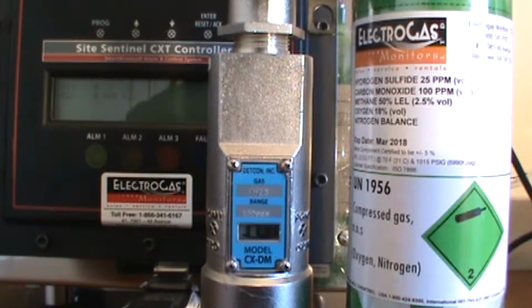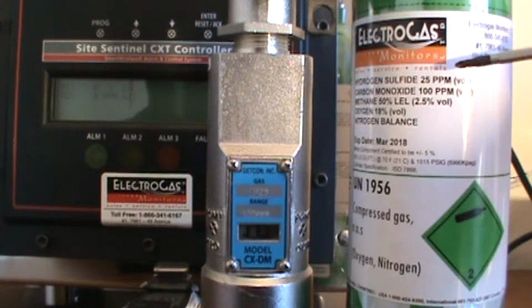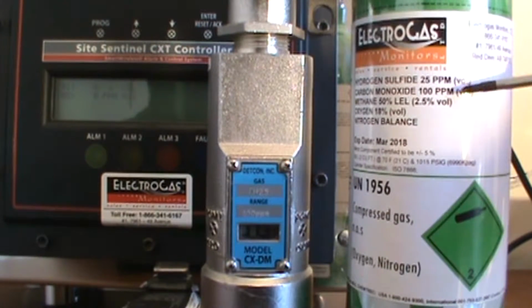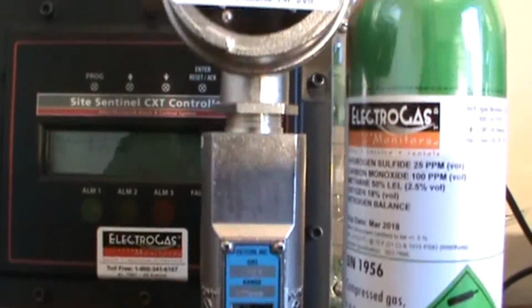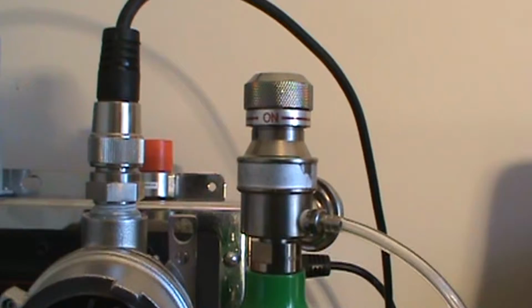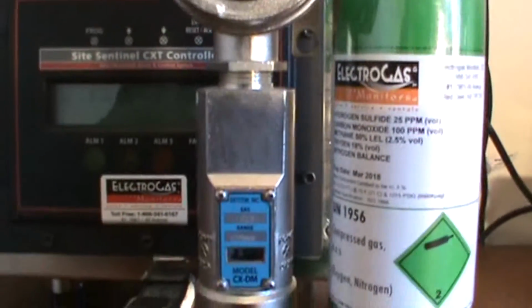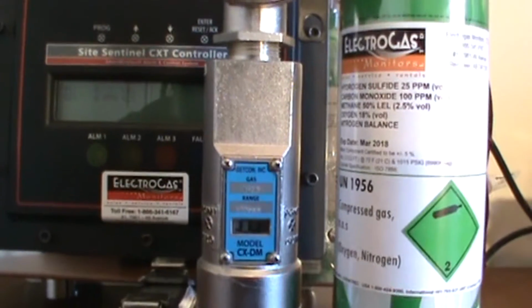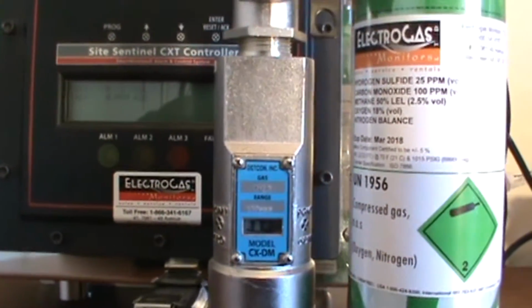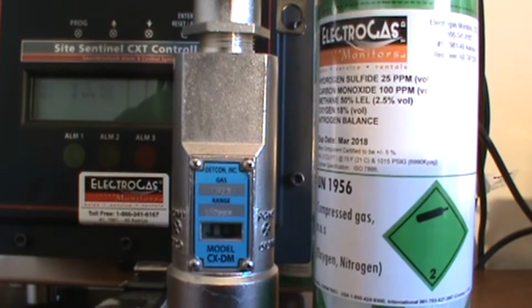So this is a very simple test. You will require proper bump test gas. We use calibration gas of 25 parts per million H2S. We use a half a liter per minute regulator and a small amount of hose, less than 3 feet. Again, there is no special mode that you go into. What we are simply doing is challenging the sensor with gas to confirm every chained piece is working properly.